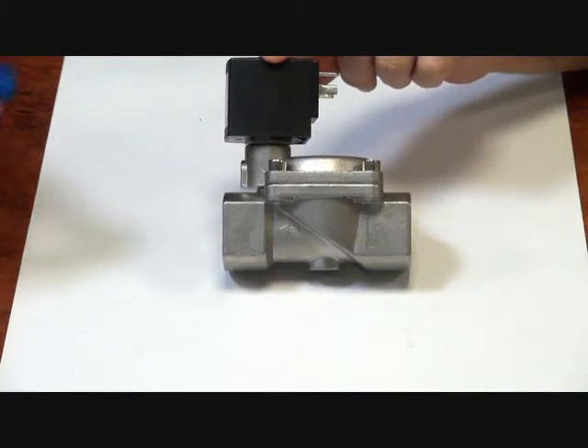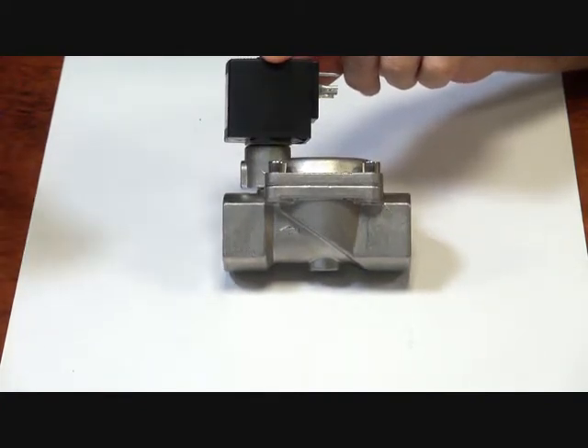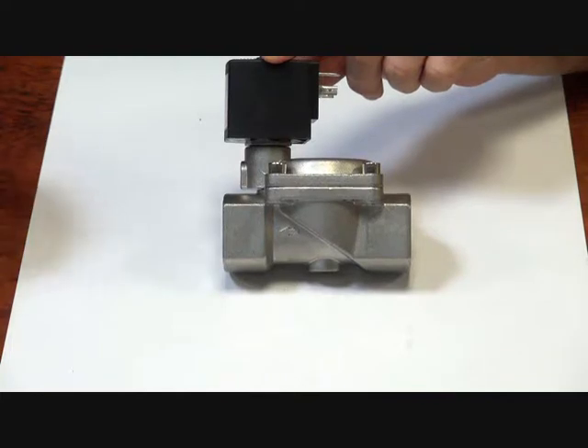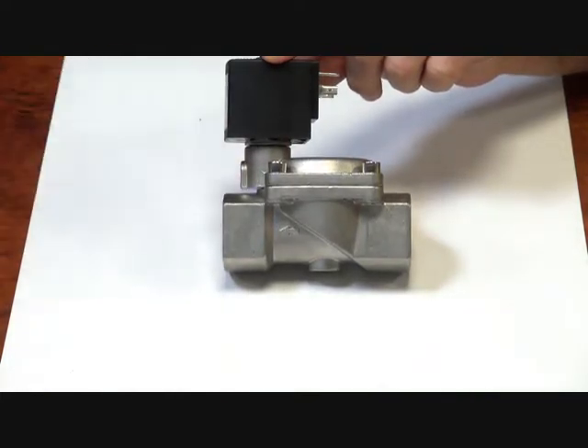So where can't you use this valve now? You can't use it in, say, tank drain, low head pressure applications, vacuum, anything where you don't get a differential pressure drop across the valve, you can't use it.